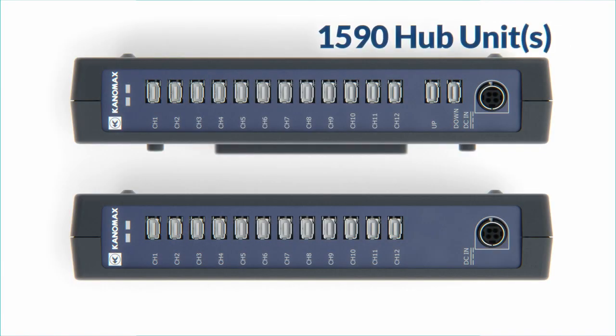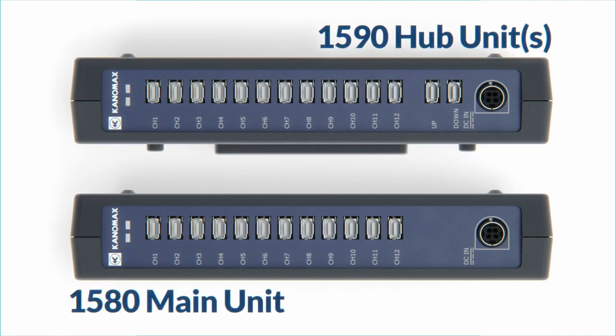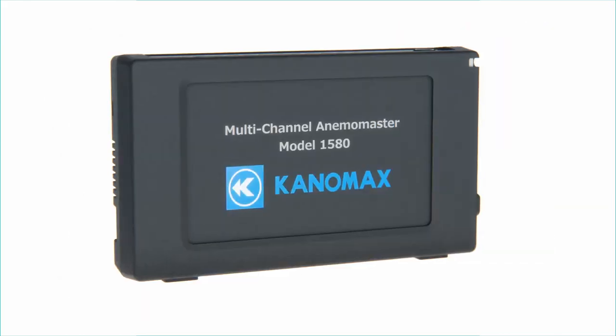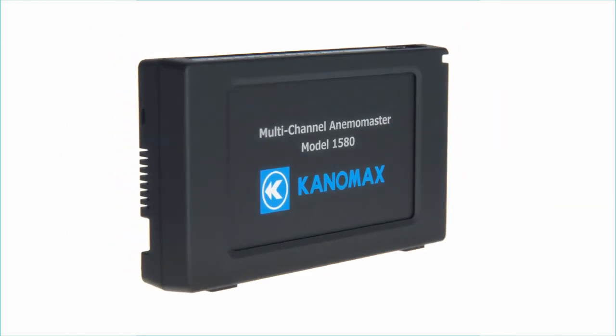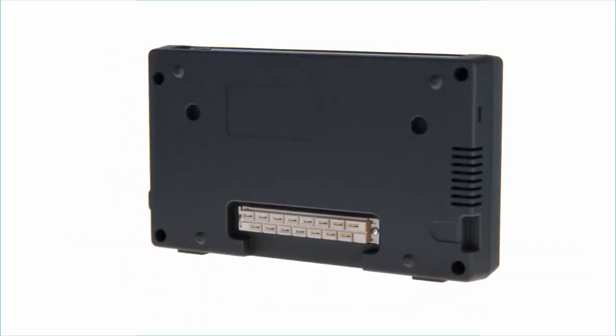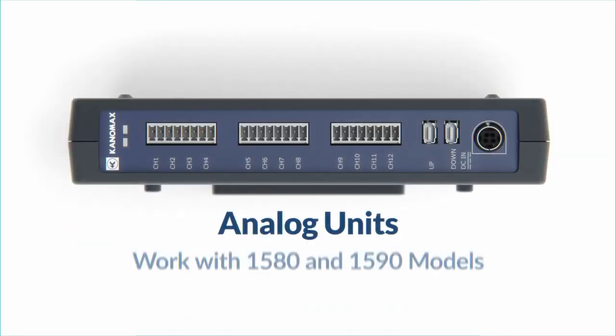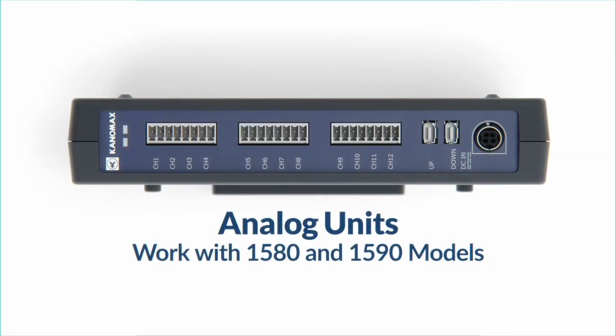1590 hub units and the 1580 main unit have 12 probe connection terminals and a DC power supply terminal. They're nearly identical, but the 1590 hub unit includes unit-to-unit communication terminals on top. In the case of the 1580, its ability to communicate with its analog unit is done via the connection socket on its back. The analog units are the same for both models and cross-compatible.